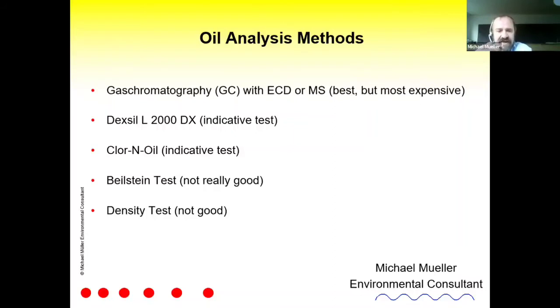Then we have the Beilstein test, which is not really good—only for an emergency case. That means you take a copper wire, put it in the oil, take it out, and light it with a lighter. If the flame is green, then we have chloride.